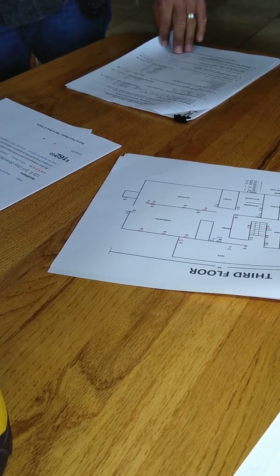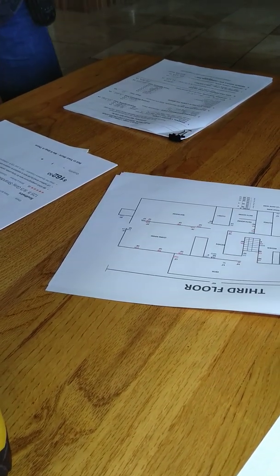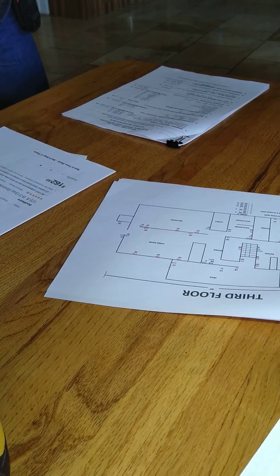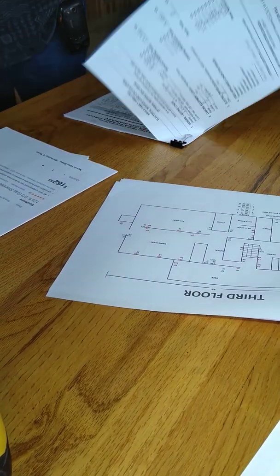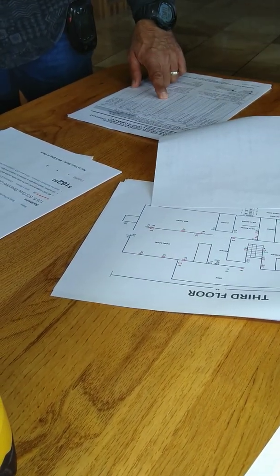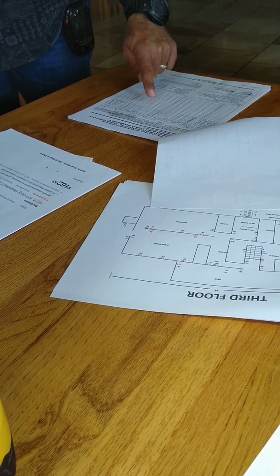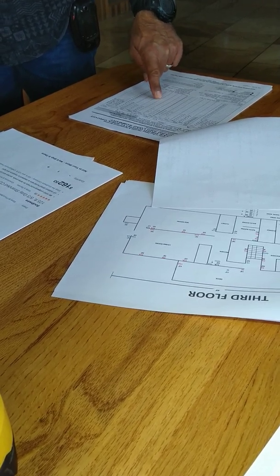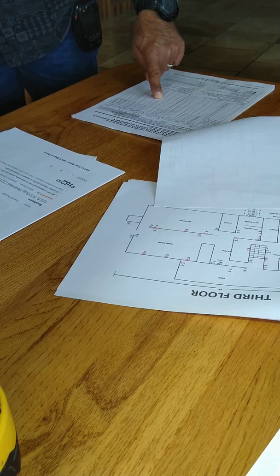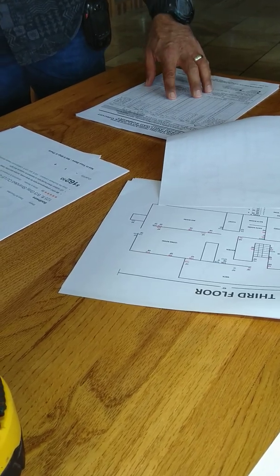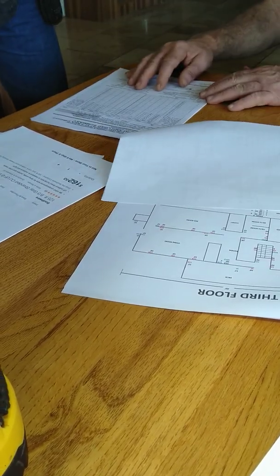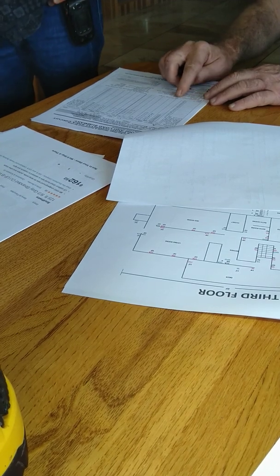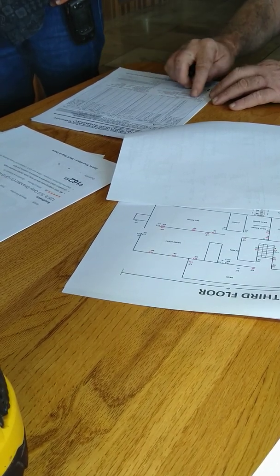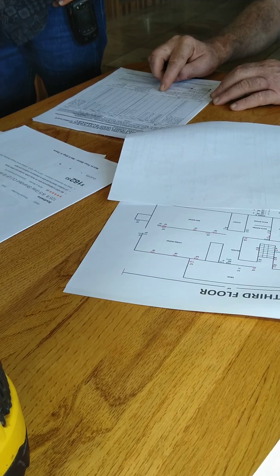Because that main service panel has feeders to each sub panel, you now have to know what size feeder you need to be able to supply that sub panel. Does that make sense? Yes. So that's what you need to have now. Okay, so that would be filling in this information here: size, number, type, and so on.